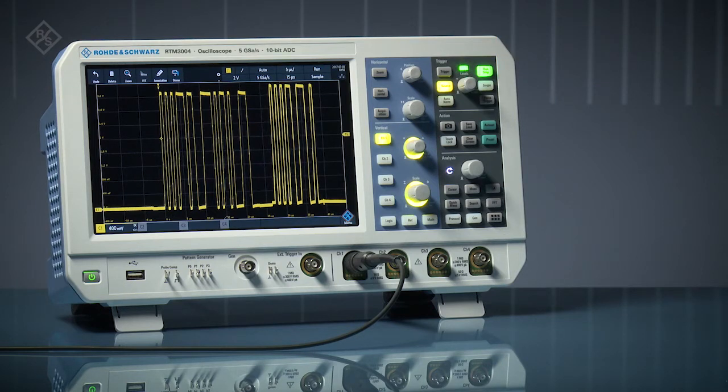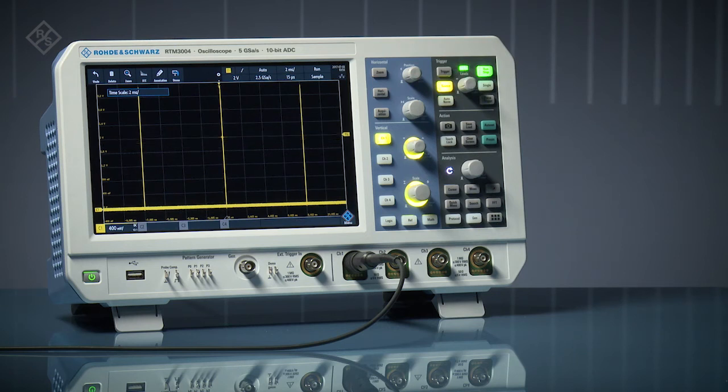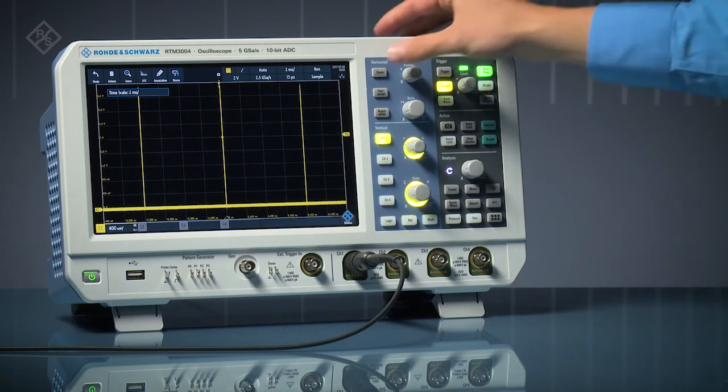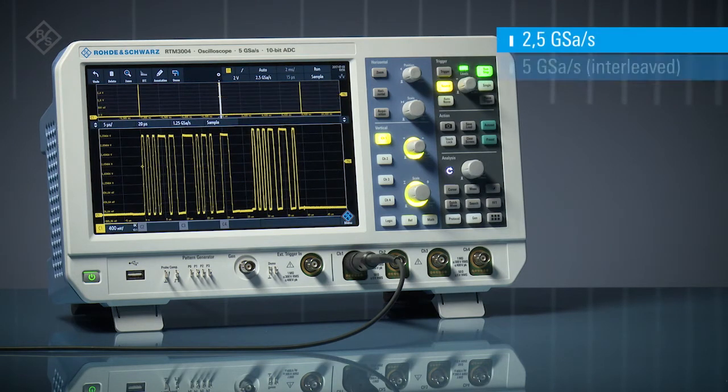Capturing longer times presents a bigger challenge. Let's increase the capture length by a factor of 400 to capture multiple bursts. When we zoom into a single burst, the scope still sees important signal detail. Deep memory allowed it to retain sufficient sample rate for full bandwidth. Scopes with less memory would be forced to reduce sample rate and miss important signal detail.